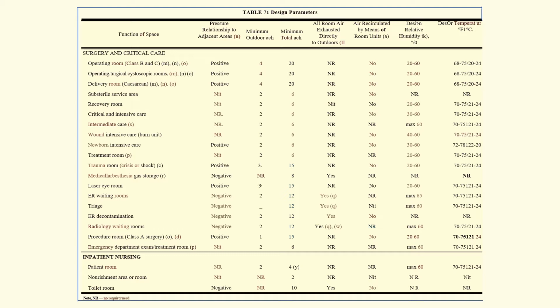Now, we did not use this table in the design of the medical office building. If you use this table, it has a very big impact on HVAC energy, similar to a lab when you use high minimum ventilation rates. It really drives up your annual heating and cooling energy.